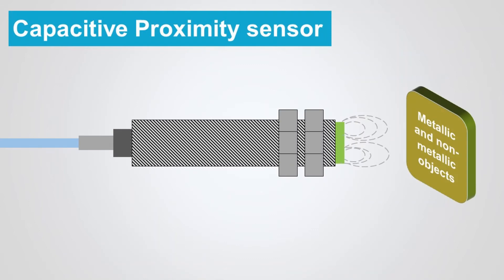Capacitive proximity sensors can detect both metallic and non-metallic targets in powder, granulate, liquid, and solid form. This, along with their ability to sense through non-ferrous materials, makes them ideal for sight glass monitoring, tank liquid level detection, and hopper-powder level recognition.